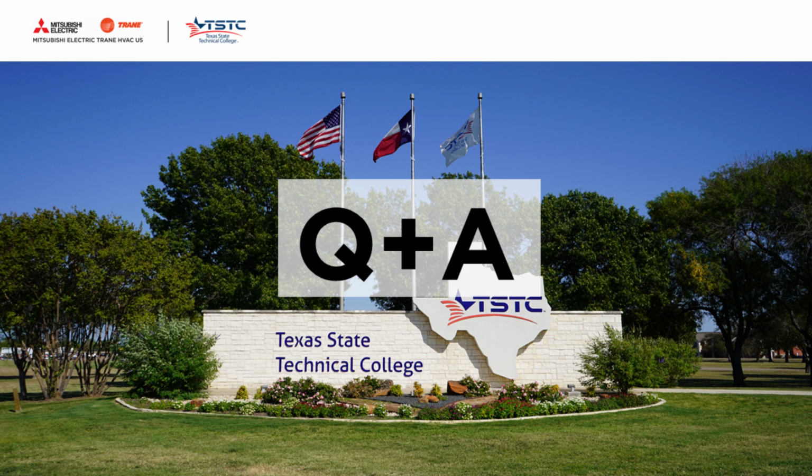What we typically recommend is perhaps more than one smaller system. And when you think system, just consider how many indoor units are connected to one condensing unit. That would be one system. So you might have two systems, maybe three systems feeding a building. And that, again, is an energy efficiency sweet spot. And in a worst case scenario, if something were to fail, then a smaller number of zones are affected.